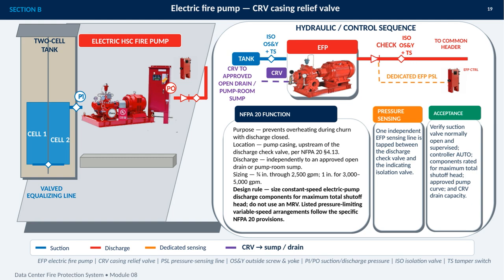The key protection device is the casing relief valve, or CRV. Its purpose is to prevent the pump from overheating during churn when the discharge is closed. It is located on the pump casing, upstream of the discharge check valve, and must discharge independently to an approved open drain or pump room sump.